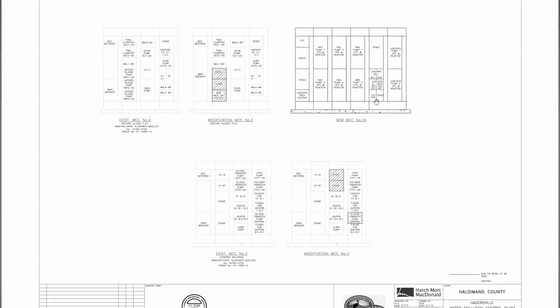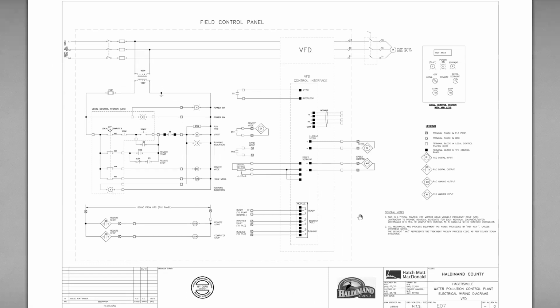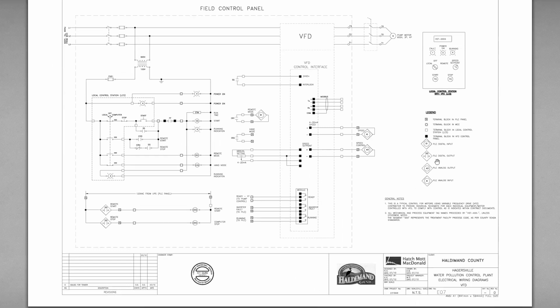So inside each one of these sections is going to be this. So this is a typical VFD drawing that this engineer has put out that outlines the function that they want to get out of the drives, but may or may not actually have the wiring exactly based on the equipment being supplied. So this is a large engineering tender drawing set that has been sent out, that has been designed to do a specific task, but not necessarily done to the level of detail where you could wire based on it.